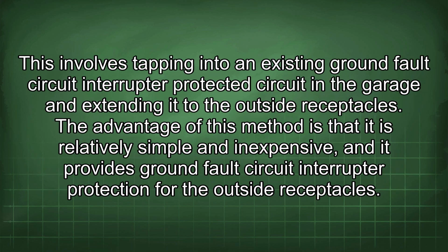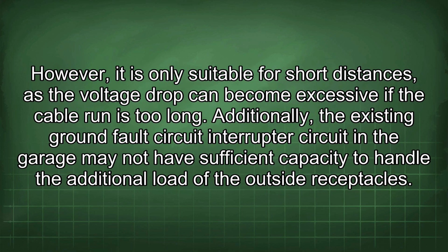This involves tapping into an existing ground fault circuit interrupter protected circuit in the garage and extending it to the outside receptacles. The advantage of this method is that it is relatively simple and inexpensive, and it provides ground fault circuit interrupter protection for the outside receptacles. However, it is only suitable for short distances, as the voltage drop can become excessive if the cable run is too long. Additionally, the existing ground fault circuit interrupter circuit in the garage may not have sufficient capacity to handle the additional load of the outside receptacles.